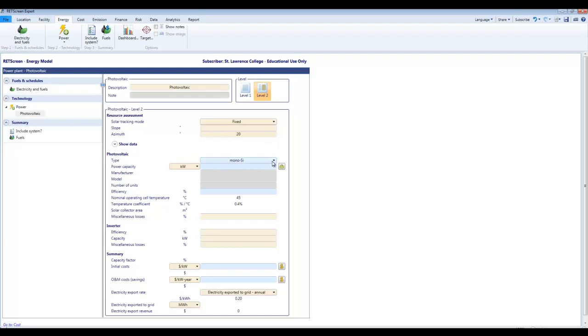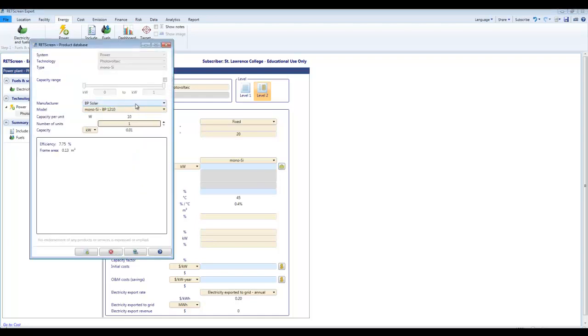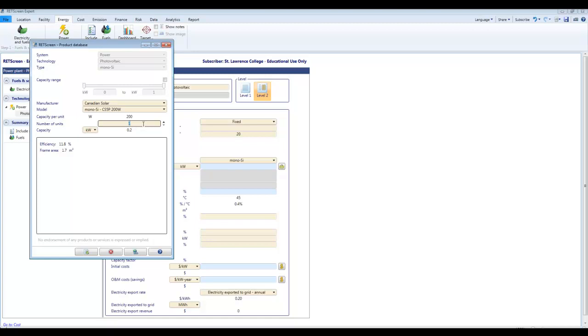I'll come back to slope in a minute. We can choose up here fixed one axis or two axis as our array type. Two axis means it's tracked on a tracker and it's going to follow the sun all day long. I'm going to do a fixed one here. We get to choose first of all under here's where we're going to tell it which photovoltaic modules we're using. First step is to choose the technology from a variety of different types. I'm going to choose monosilicon and come in here and now I can go to a product database. I'm going to choose a Canadian solar module and I'm going to choose a 250 watt module or maybe a 200 now. Choose a 200 and hit the check mark here and it will just paste in now the data for that. One more thing I want to choose the number of units here. Well 50 units would be 10 kilowatts. I'm going to pick 100 units which will give us 20 kilowatts. You can see it's calculated that down below.